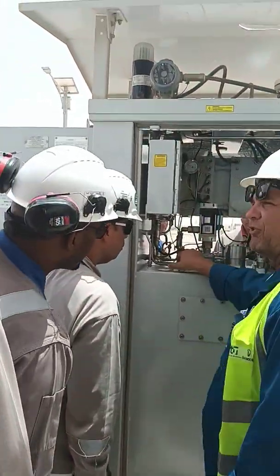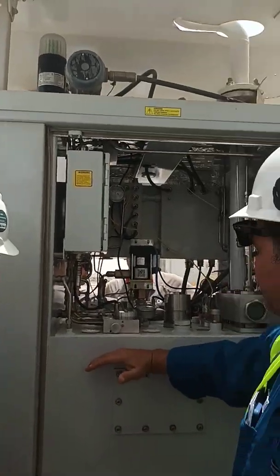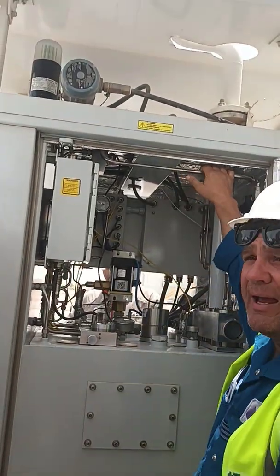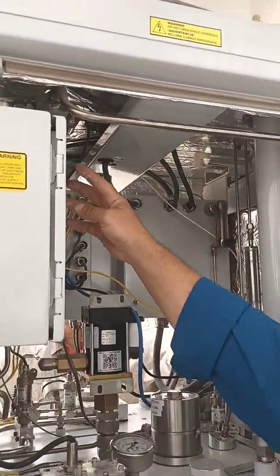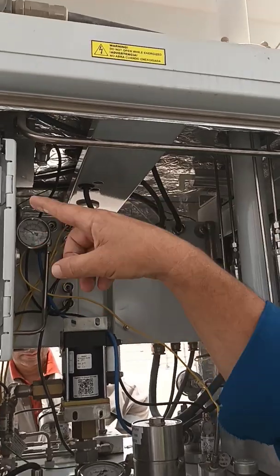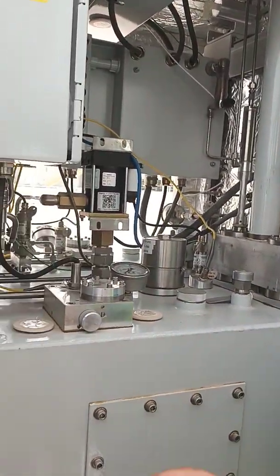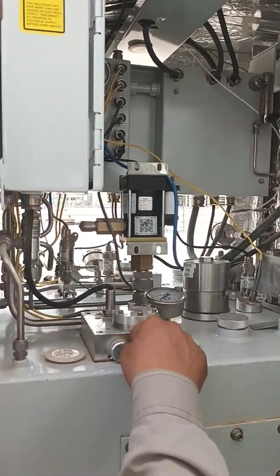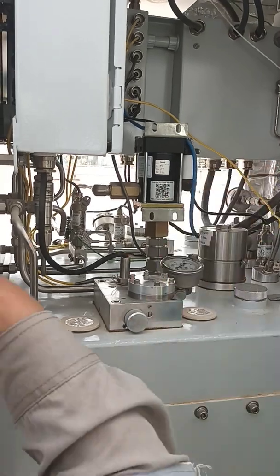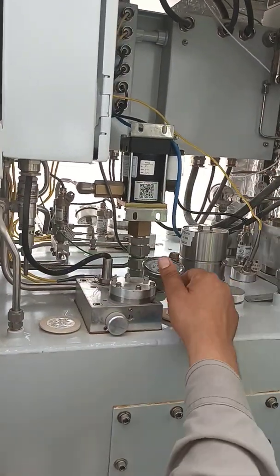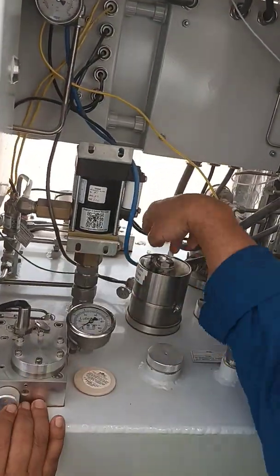This is the mixed head for the auxiliary. This is the one that is mixing the air with the oil right now from this tank. That's your air supply, which I showed you before, right? Yes. So the air supply, I told you, is divided by 3. So you can see the 3 valves in the front. Then you have 3 regulators as well. So this one is mixing now. This is the one making the oil mist now. Yeah, mixing, because it switches. You change it because we're running the auxiliary. Now we put the normal one. Is that one there? You see, it's the same. So you've got 2 of the same.